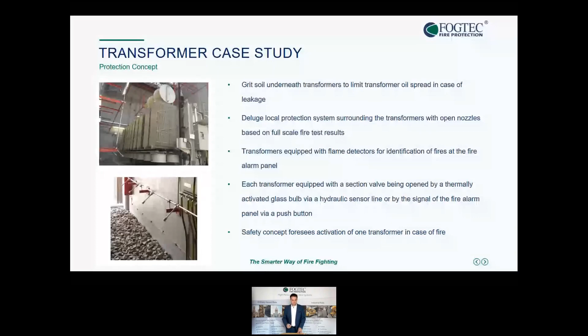The activation of the system was by fire detection system. In this case, there was a special request for a mixture of glass bulb activation and the fire detection system, whereby this was a customer request. In water mist systems, you are generally flexible with the chosen detection system for the application.